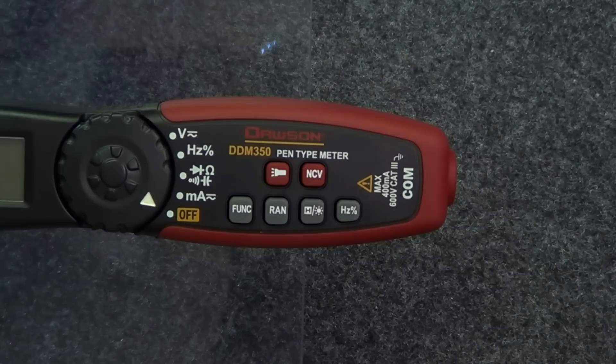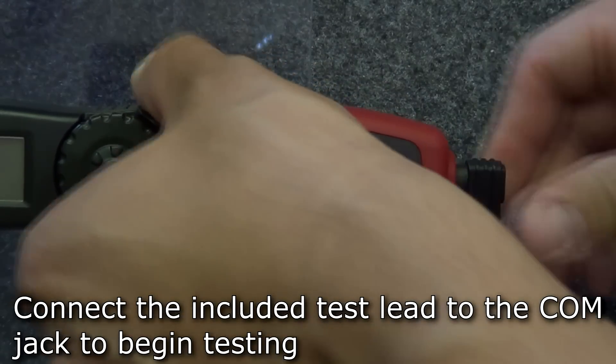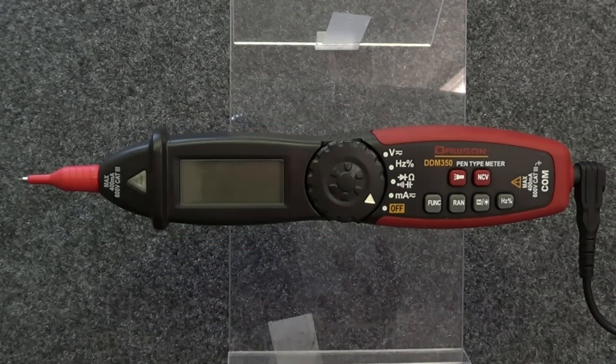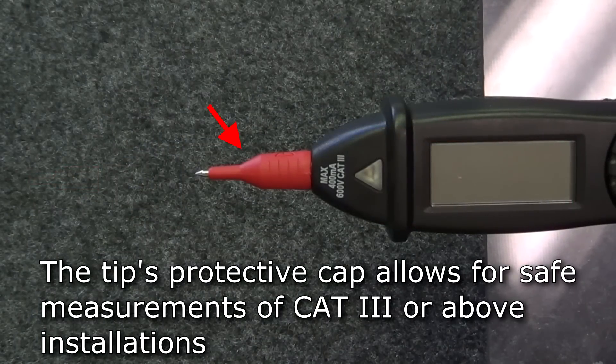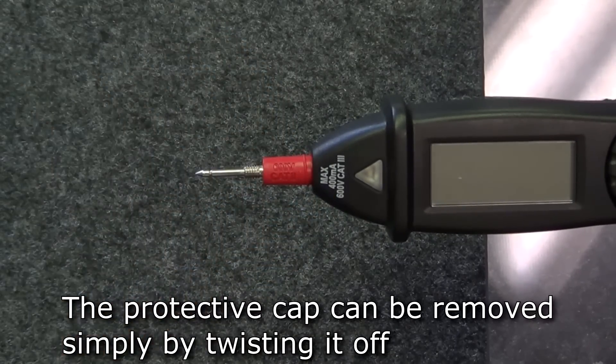In any mode, to begin testing, connect the test lead to the COM jack. The tip of the meter acts as a positive connection and the test lead as the common end. The tip also comes with a protective cap, making it safer when making measurements on Cat 3 installations. The cap can be removed simply by twisting it off for making measurements on Cat 2 or lower installations.